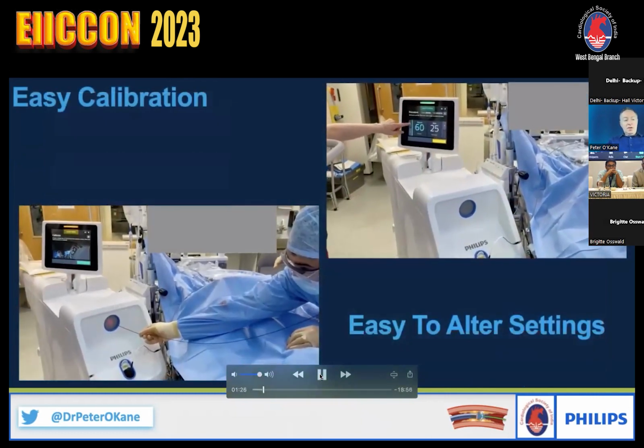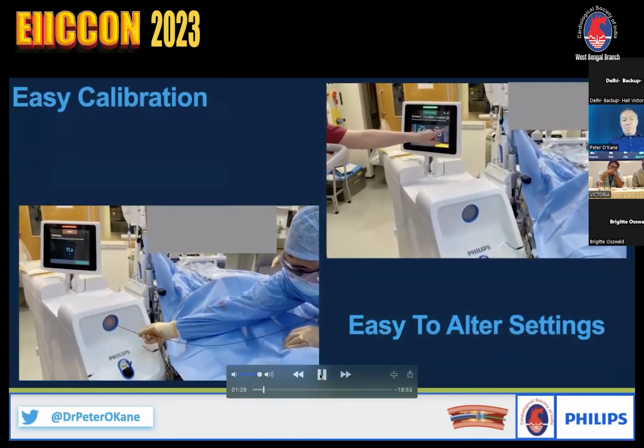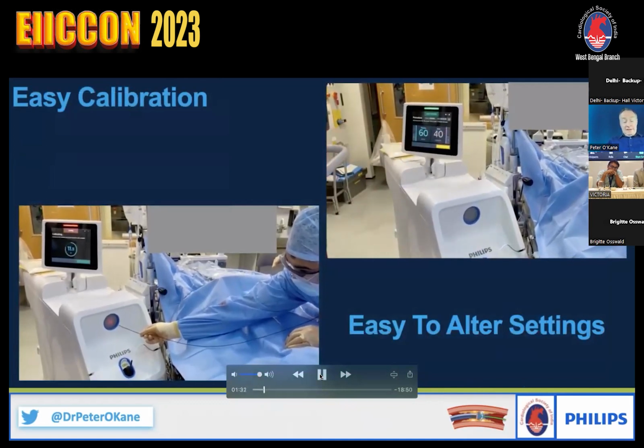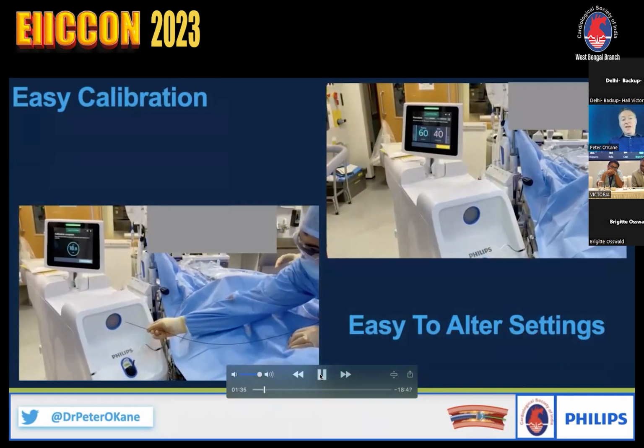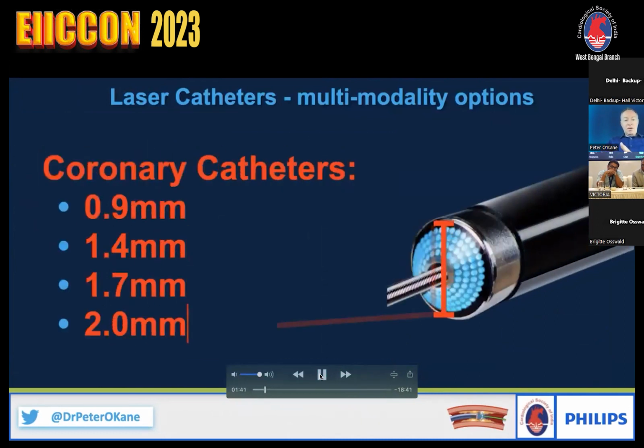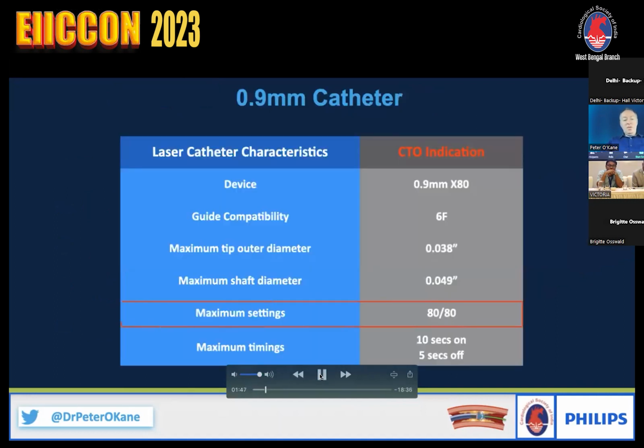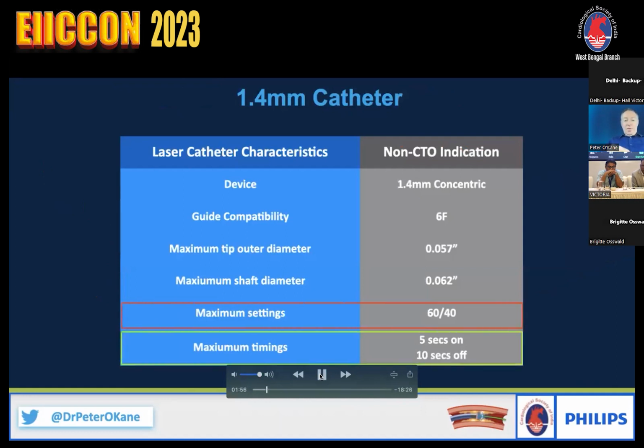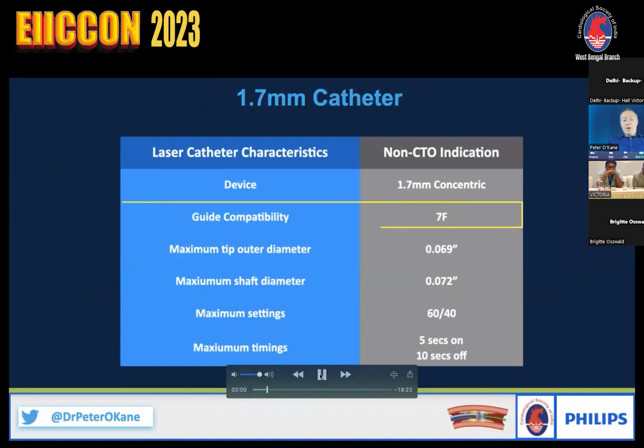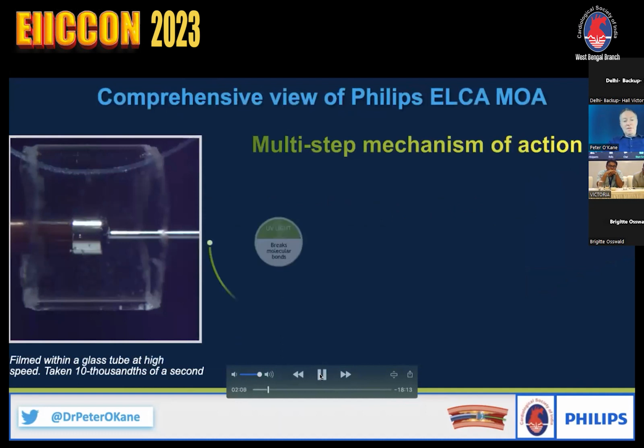Calibration is identical. You hold the catheter against the machine, but now there's a touch screen which really facilitates much easier moving around from different energy settings, which I'll talk through in a second. In terms of the catheters, there's obviously not just coronary work, but there's lead extraction, which you'll hear about later. The coronary catheters, there are 4 catheters. The 0.9 is the only one to worry about or think about. It offers the maximum energy and the highest laser settings. You get 10 seconds of lasing versus 5 seconds rest. The 1.4 is 6 French compatible, but has lower energy settings, the 1.7 is 7 French compatible, and then the largest catheter is 2.0 and is 8 French compatible. But those all have lower settings in terms of power.